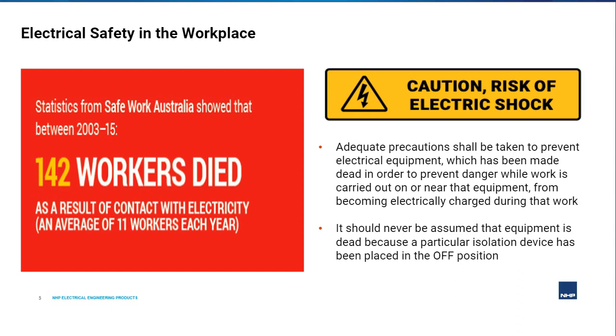An example, back in 2002, Queensland Mines Inspectorate issued an alert after a plant operator in a mine in Queensland isolated an energy source to a pug mill just to carry out a daily cleaning task. Unexpectedly, the pug mill started up, and the reason was that an internal aluminium shaft inside an isolator had broken and allowed the handle of the switch to rotate to the off position without actually isolating the energy source. So the isolation was ineffective, and then the equipment obviously is inherently unsafe.